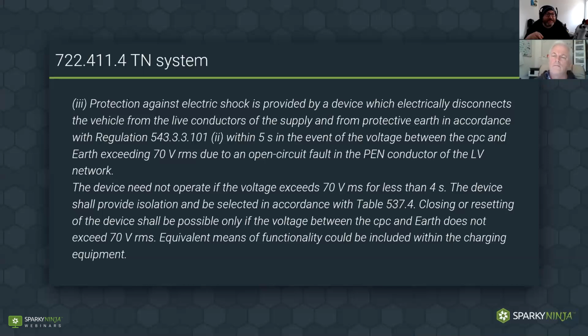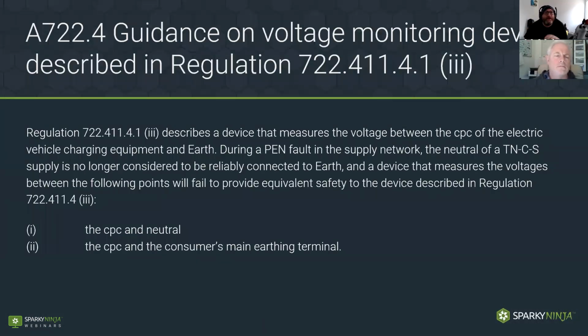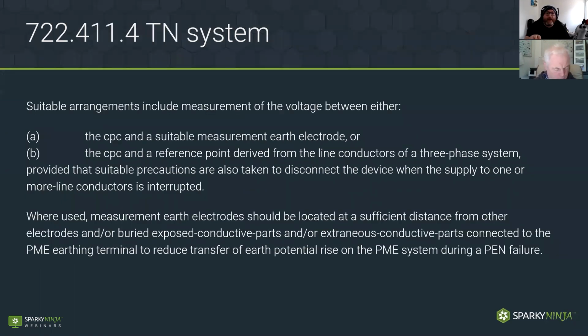And the guidance in the annex says that this describes a device measuring the voltage between the CPC of the electric vehicle charging point and earth. That's a big E, so that's got to be a measurement to true earth. During a PEN fault, the neutral of the TN-C-S supply network is no longer considered to be reliably connected to true earth. Therefore, it's not suitable for the device to take measurements to the CPC in the neutral and to the CPC in the consumer unit's main earthing terminal. So these two connection methods are not suitable. We need to find a way to take a CPC to a suitable measurement earth electrode. So a little electrode that comes off the device and goes into true earth, okay?